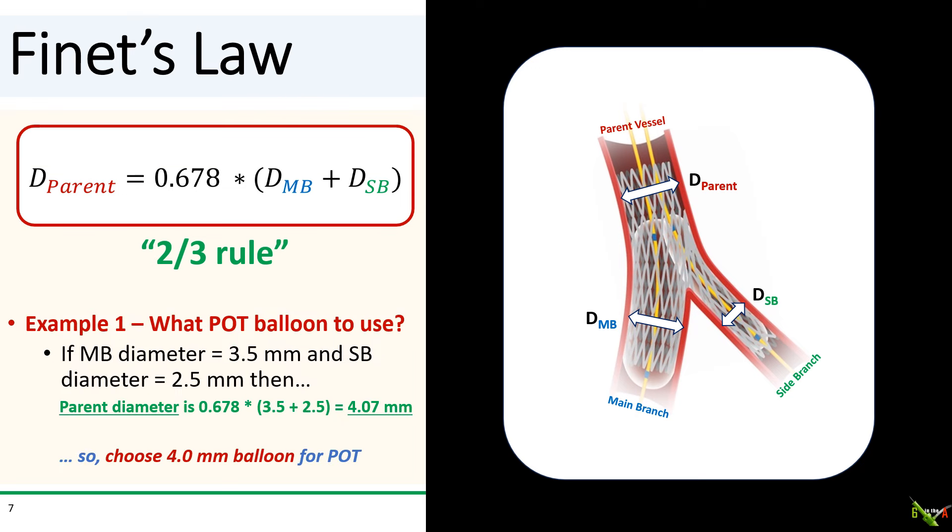So how do you use Finet's law? Well, suppose you were trying to figure out what POT balloon you needed to use in a bifurcation case. Well, in this case, if your main branch is 3.5 millimeters and your side branch is 2.5 millimeters, then by Finet's law, the parent vessel diameter should be 4.07 millimeters. So rather than choosing haphazardly, you've now just calculated that you'll need to choose a 4.0 millimeter NC balloon to do your POT.